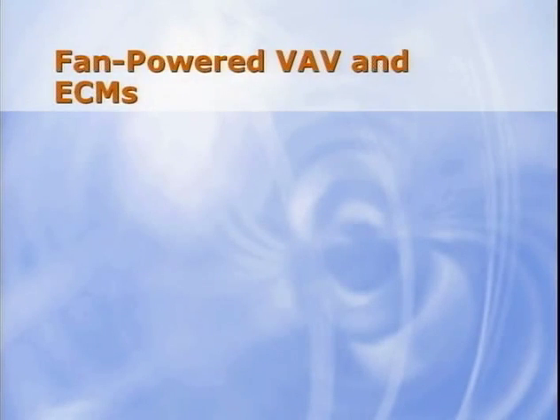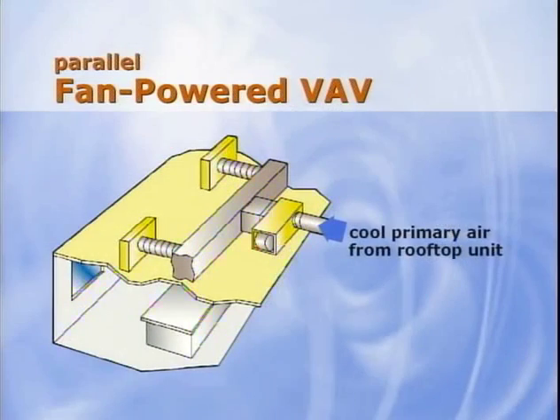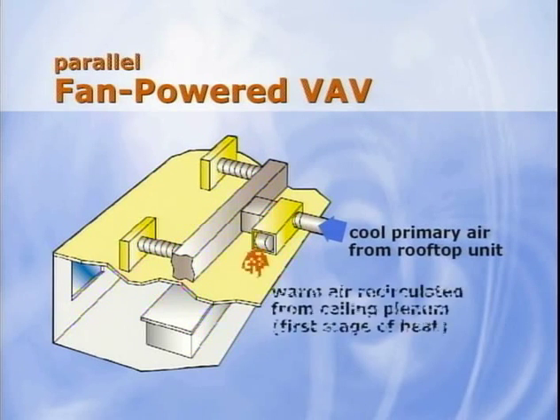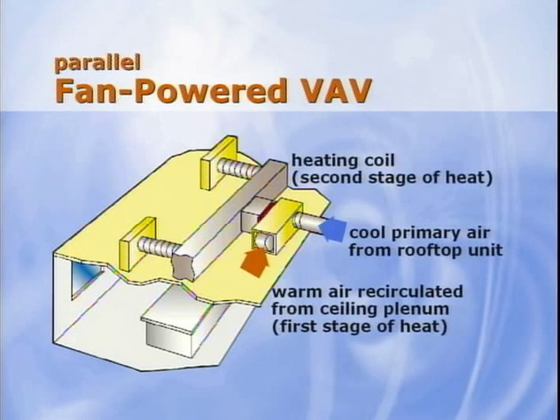Next topic, fan-powered VAV and ECMs. Heat generated by light fixtures warms the air in the ceiling plenum. Fan-powered VAV boxes use this warm air from the plenum as a form of energy recovery. In a parallel fan-powered VAV box, primary airflow is reduced as the cooling load decreases. When the box reaches its minimum airflow setting, the small fan activates to draw warm air from the ceiling plenum and mix it with cool primary air from the rooftop unit. If more heat is required, the heating coil can be activated.